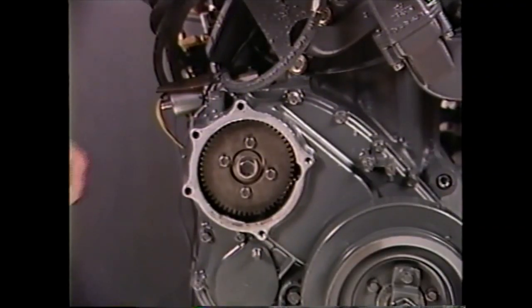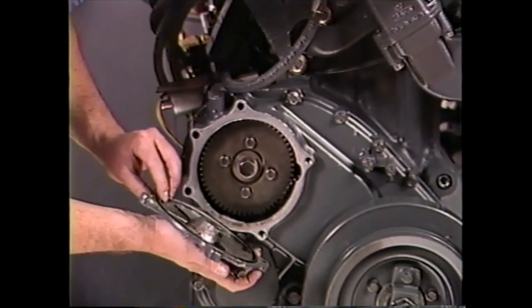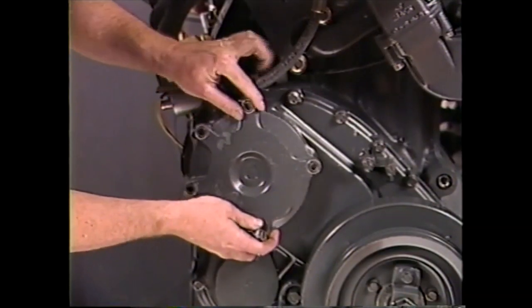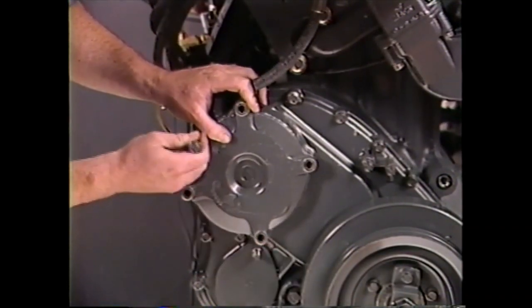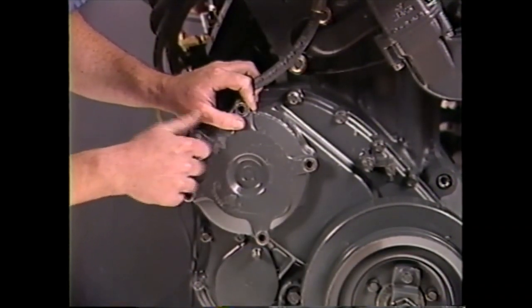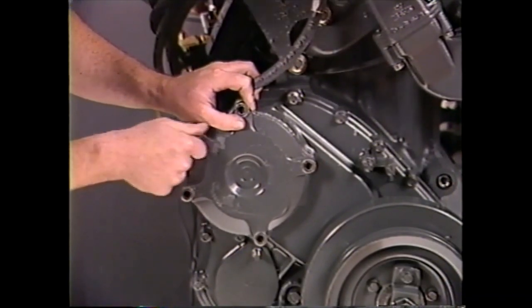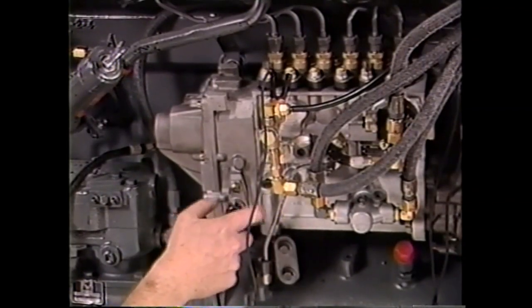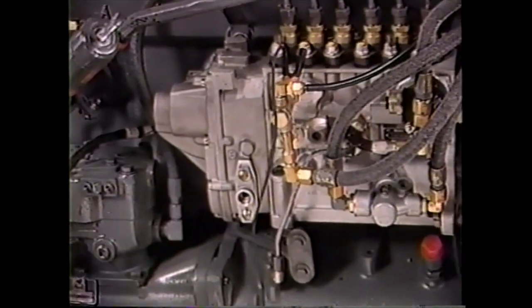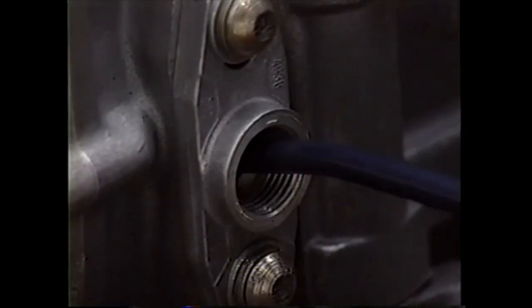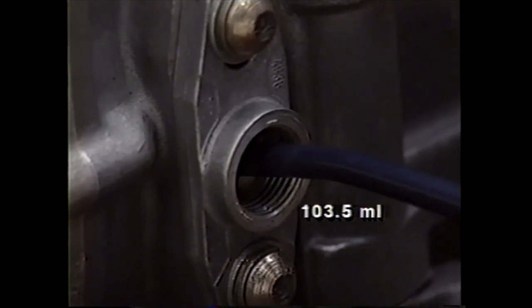When the timing is correct, lubricate and install a new O-ring on the cover. Then install the cover on the engine and torque the cover bolts to specification. Remove the position sensor. Pre-lube the governor by adding 3 1/2 ounces of engine oil at the position sensor bore.